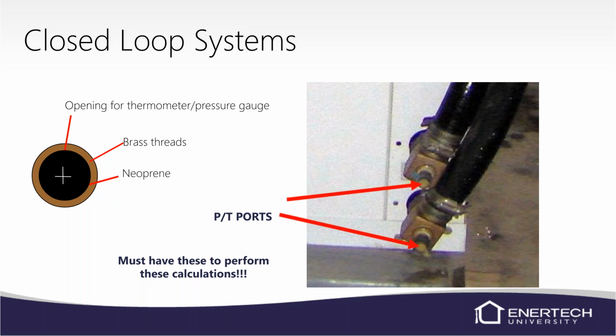So this is basically the opening for the thermometer and the pressure gauge, a little cutaway of it. It's got a little neoprene gasket in there. There is a cap that's got a gasket on it as well. Over time, the neoprene will get a little bit weaker, maybe even get a crack or so in it, and it may spray out a little bit when you pull your thermometer out. Not a big deal. Just make sure you don't lose the cap, and that'll seal it back up.